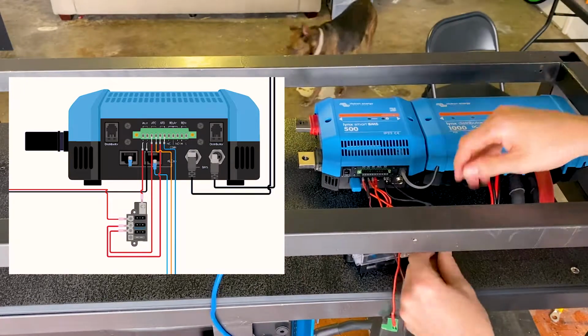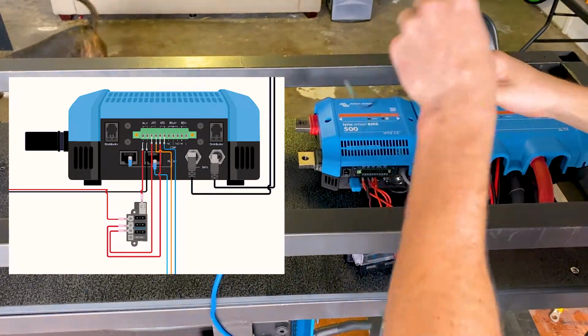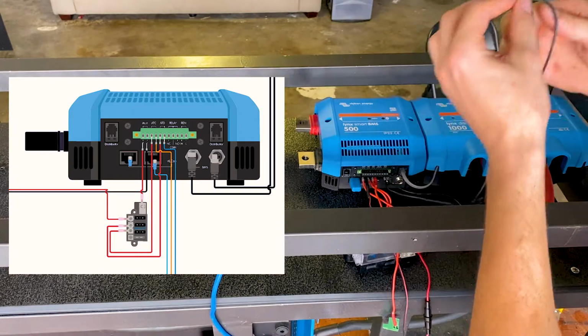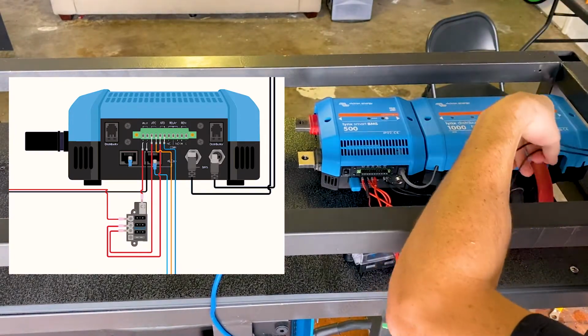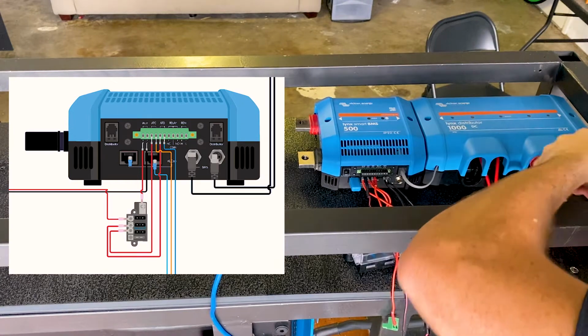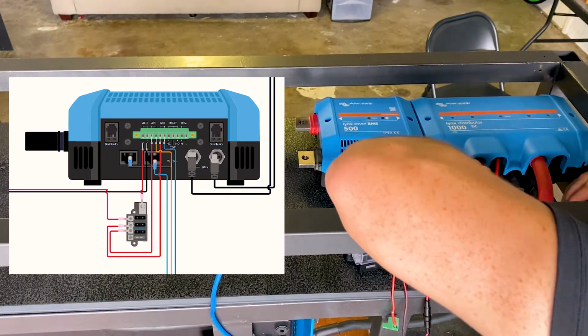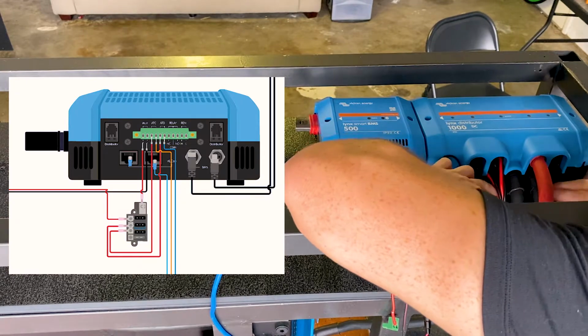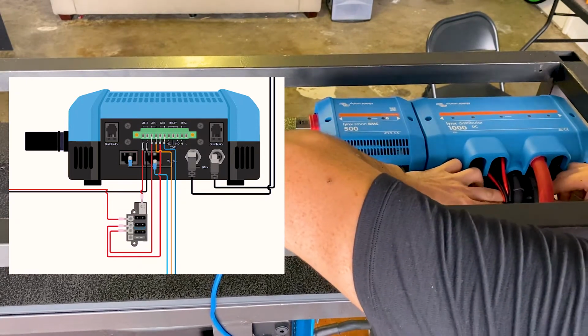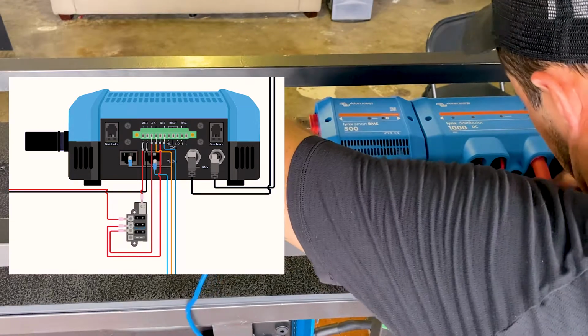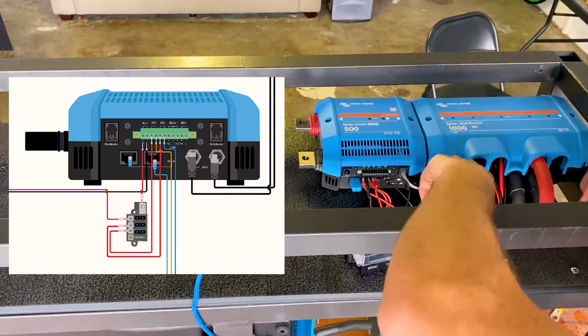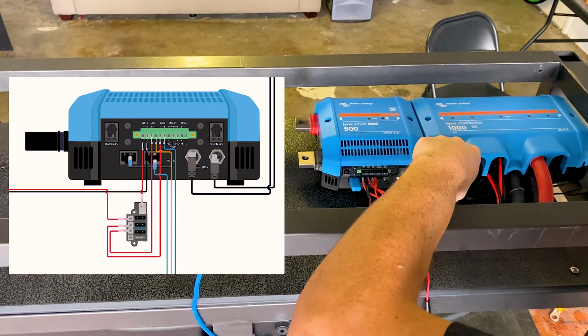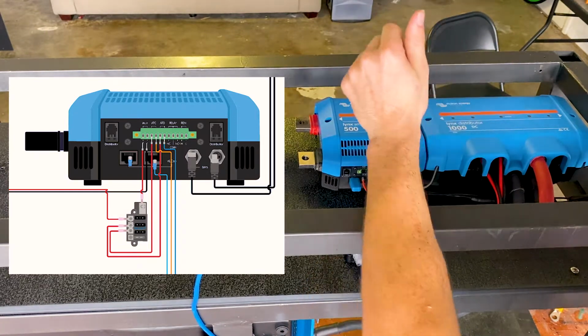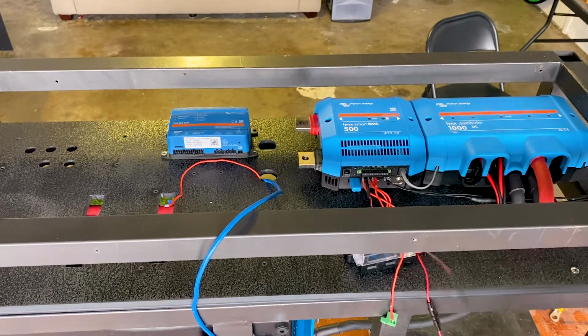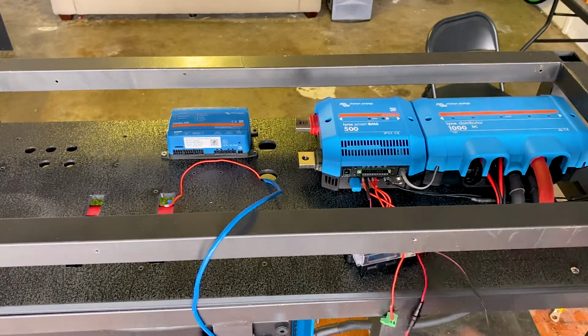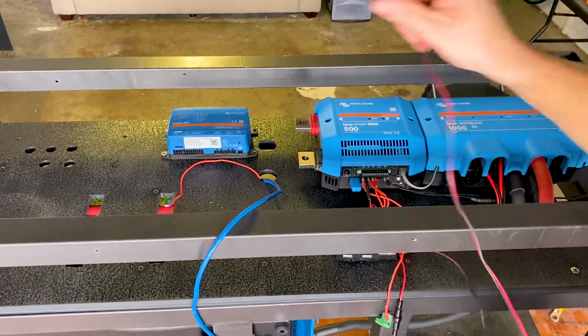I'm going to plug that into the BMS, and those two black wires are wired into numbers 10 and 11 on the bottom of the BMS. These will get run over to the edge of the box where the outlet will be mounted, and there will be a switch those are wired into, which will become your system on-off switch, cutting power to the entire system. So if you ever have to do maintenance, upgrade, or update it, you have that master on-off switch right next to the outlet, which is a really nice feature to have for any system, and is really the proper way to do it.